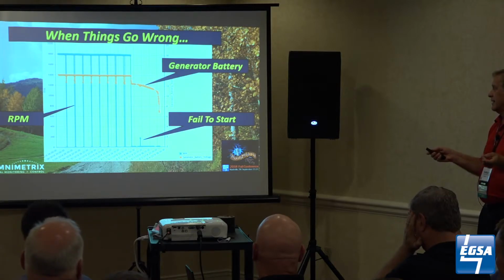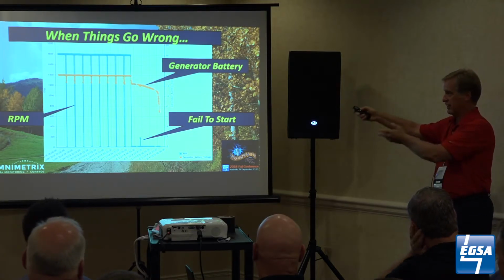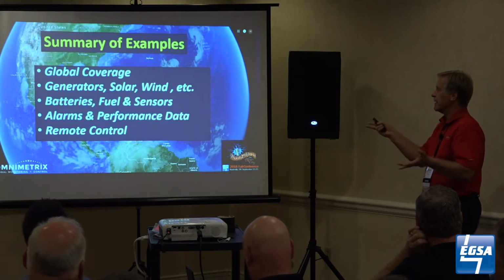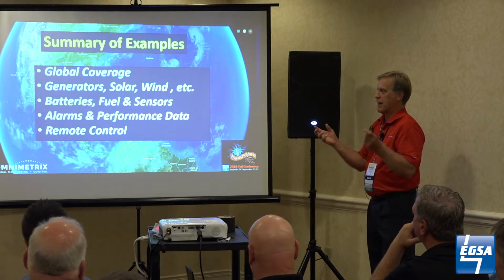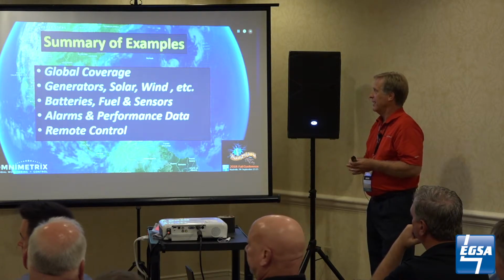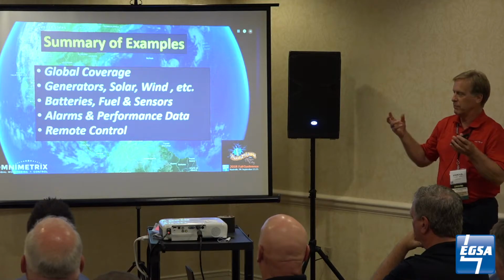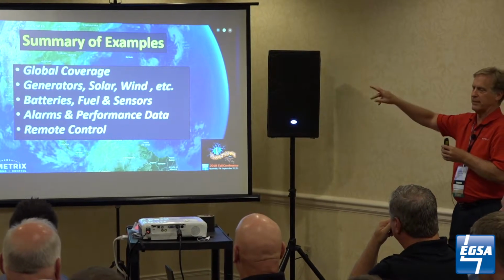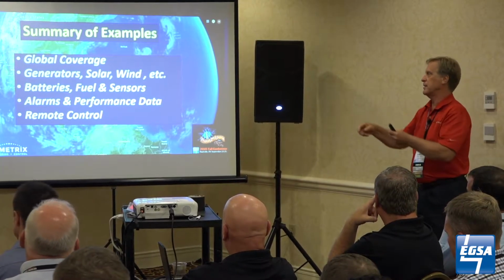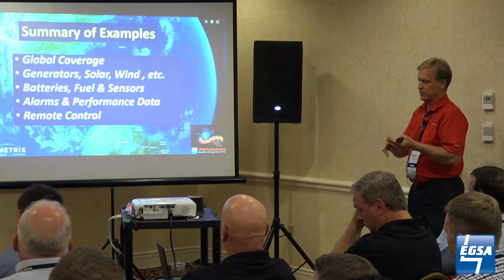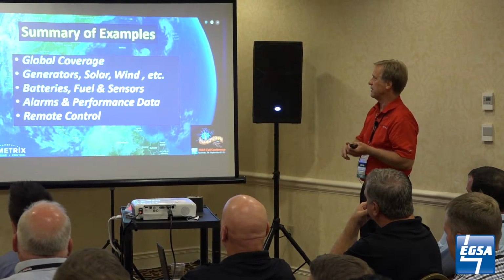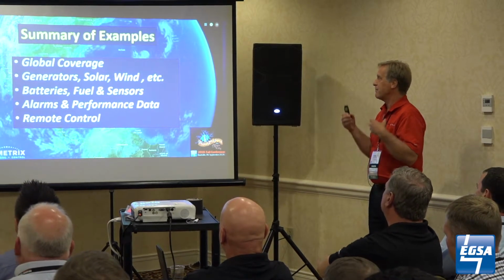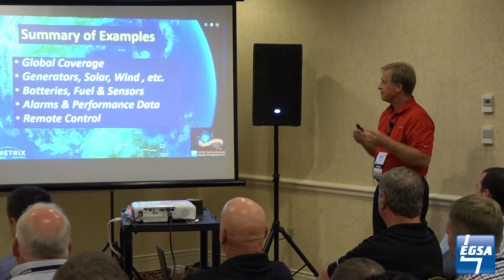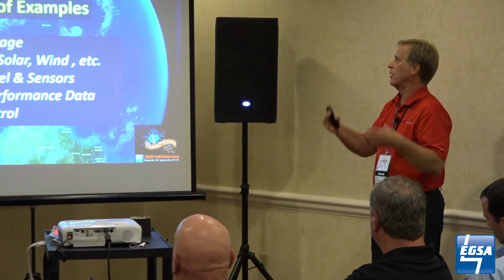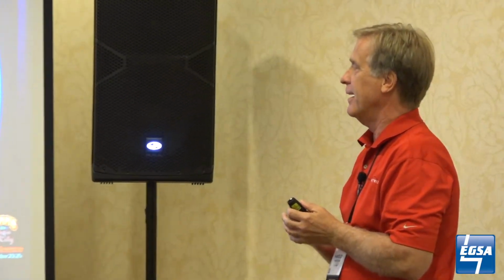So sometimes things go wrong, and of course, this is what remote monitoring is all about. That will tally up on my Nanogrid application. So the bottom line is you can do this kind of thing. We're very Modbus oriented, so every bit of data you saw is the result of Modbus access to genset controls, chargers, or other data acquisition modules. You can do it everywhere, and according to the spirit of the Microgrid group, these are examples of both solar and generation, with some reasonable examples of performance data from those.